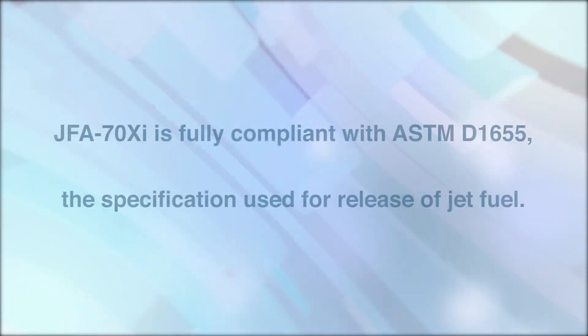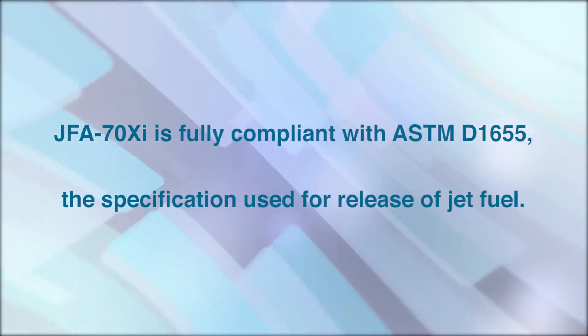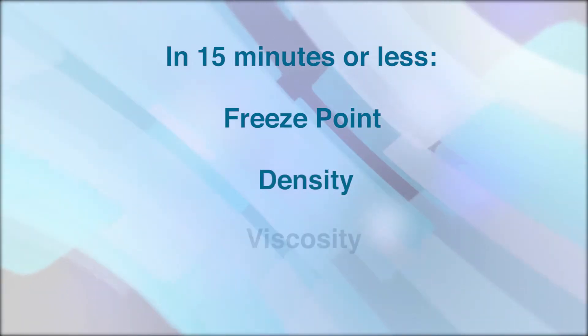Fully compliant with ASTM D1655, the specification used for the release of jet fuel. You can run three critical tests in less than 15 minutes in a single instrument. Freeze point, density and viscosity both at minus 20 degrees Celsius and at minus 40 degrees Celsius.